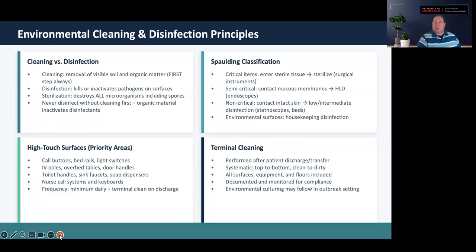Now, semi-critical items are pretty common, right? And these are ones that come in contact with mucous membranes. So a great example of this would be a flexible endoscope, whether it's used from the top down or the bottom up. Those are still flexible endoscopes. They require high-level disinfection. Another common example is laryngoscope blades and handles. Those are commonly high-level disinfected. However, we have found that we are not very compliant with that with laryngoscope blades and handles. And so we've seen many of our hospitals have moved to disposable blades and handles for that reason, because we're not really good and compliant with the safety associated with high-level disinfection. So outside of SPD, it's not something that we really recommend.